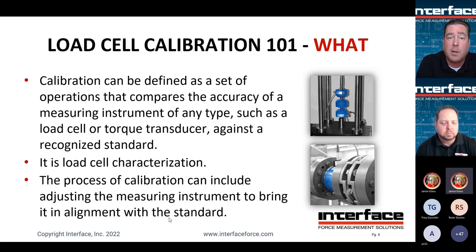That said, this calibration process can include some sort of adjustment that is done mostly on the system level, to bring that measurement system back into the tolerance or back into alignment with the standards being compared against. Next slide, please.